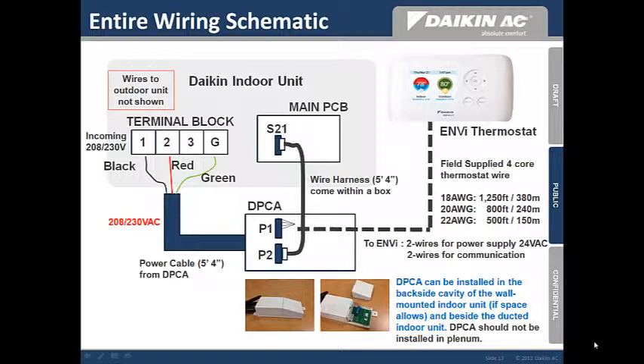Here is a summary of the wiring schematic from the indoor unit to the DPCA module, including the connections to the ENVi thermostat. The DPCA comes equipped with an attached power cable designed to connect directly to the indoor unit terminal block. The supplied wiring harness connects P2 of the DPCA to the S21 connector on the main PCB of the indoor unit. The DPCA can be installed in the backside cavity of the wall-mounted indoor unit if space allows, and beside the ducted indoor unit. The ENVi thermostat connects to P1 of the DPCA using standard thermostat wire.